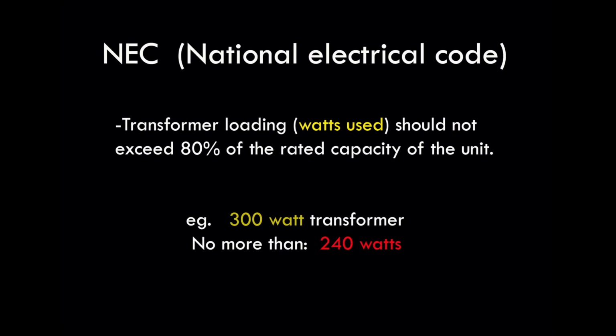As an example, if we have a 300 watt transformer, if we were to add up all the wattage of all of our bulbs that we're using in our lights, we should never exceed 240 watts, which is 80% of the 300 watt load. The reason for this is that there is actually a component of wattage or load from the power simply having to overcome resistance as it travels through the wire. In some cases, this can be as much as 20% of the total load.